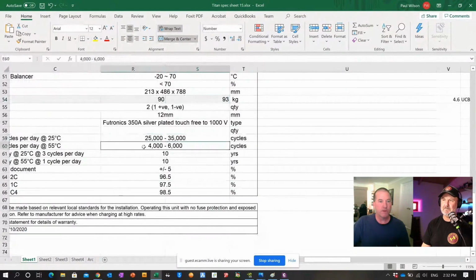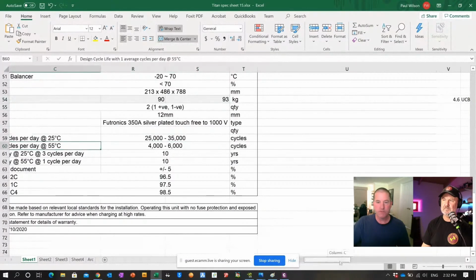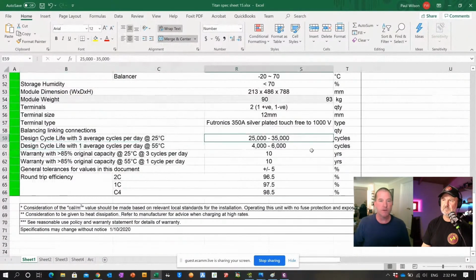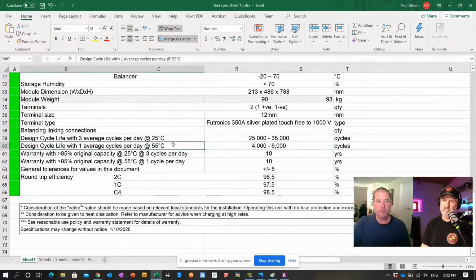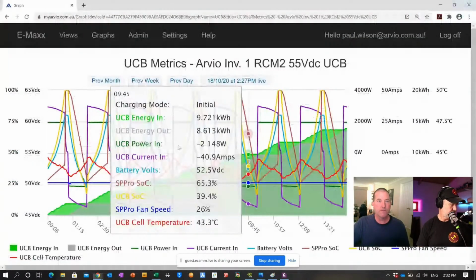Okay. If we run it very hot, so one of the tests somebody asked me to do was, well, it's all well and good to say it's going to run 25,000 cycles, but what if it's really hot? So that's why we're running that test module at 45 degrees Celsius. If you're under the 55 degrees Celsius, the design life is only 4,000 to 6,000 cycles, which is about 15 to 17 years. But not many people would need to run it at 55 degrees 24 hours a day. That'd be pretty rare. So we figured we'll test it at 45 degrees Celsius, which is probably the hottest it's going to be anywhere. And then we'll do it continuously at that rate at 1C, and we'll see how much degradation we get, at the 5-year mark and the 10-year mark, the simulated 5-year and 10-year mark. At the moment, we're only up to 4 years simulated because we've only been cycling at that high rate for 4 months.